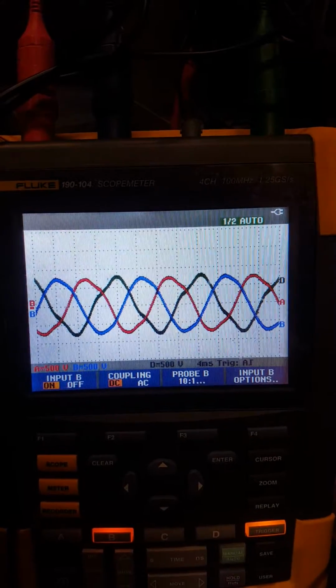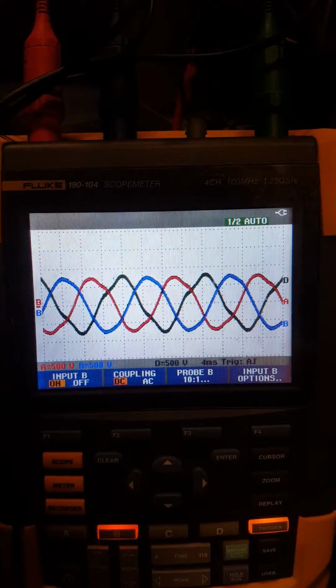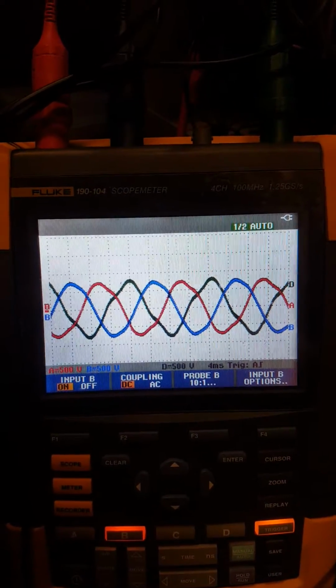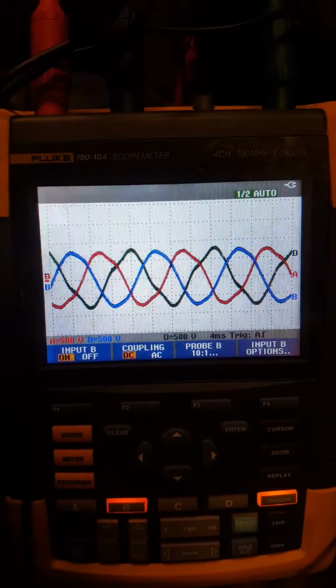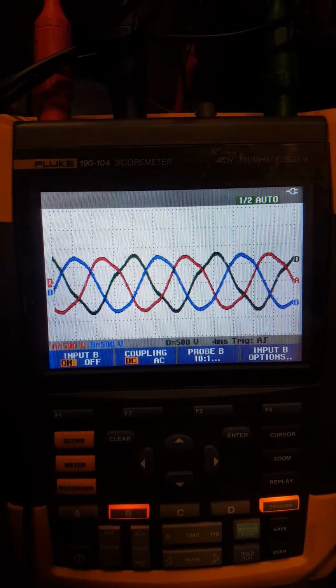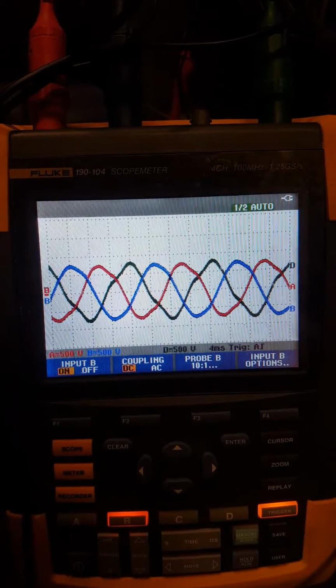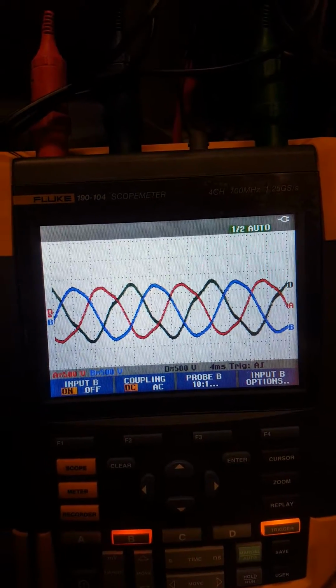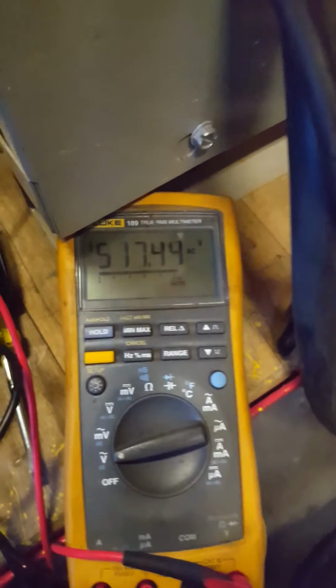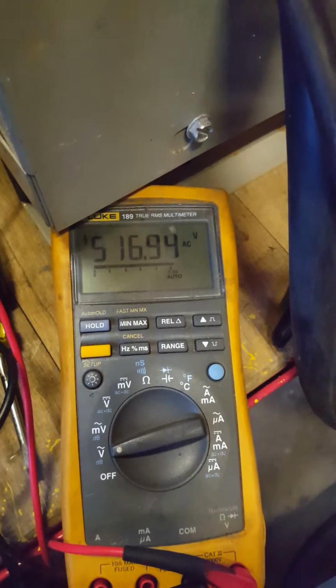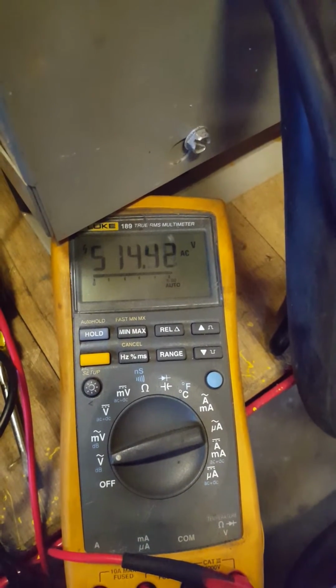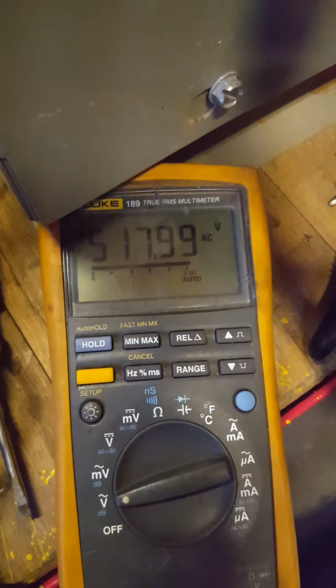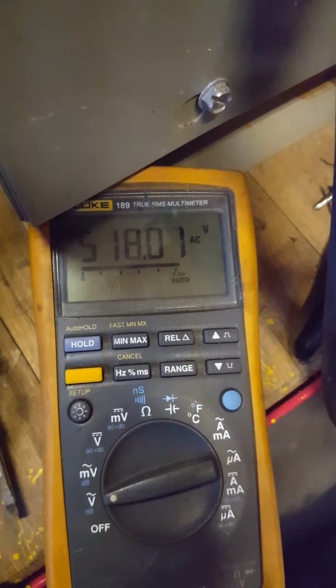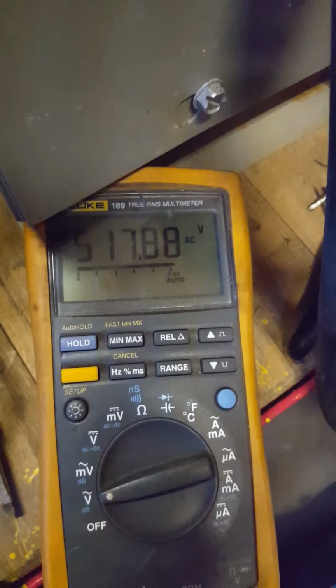Those are weird waves, but I've seen worse. Let's see, 500 volts per division. I'm not going to do the math. Let's put a multimeter on it. L1 to L2, 516 volts. L2, L3, 520 volts. L1, L3, 517 volts.